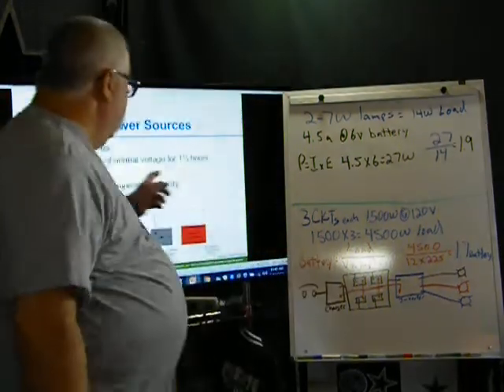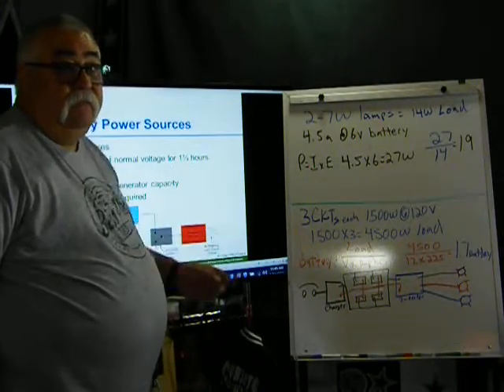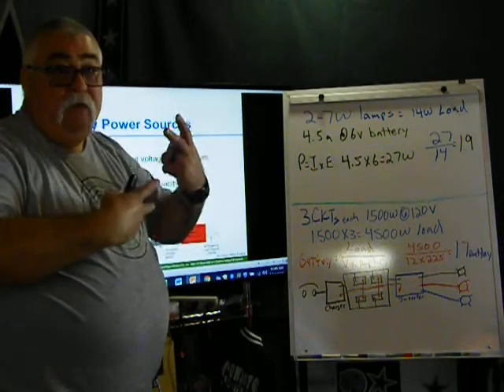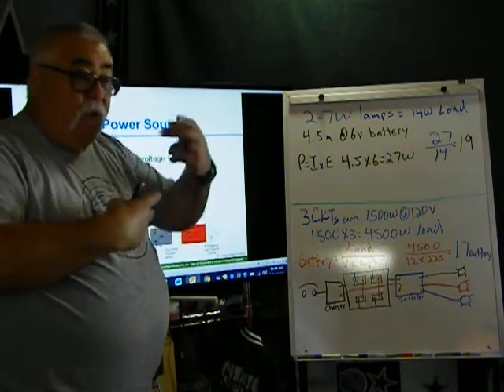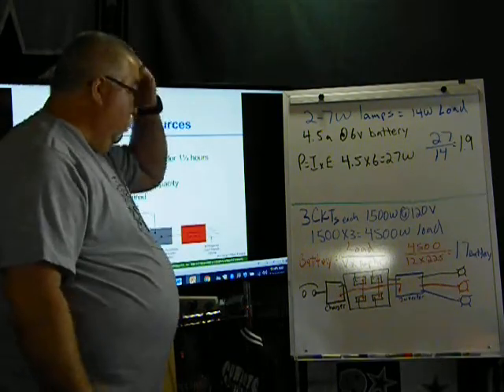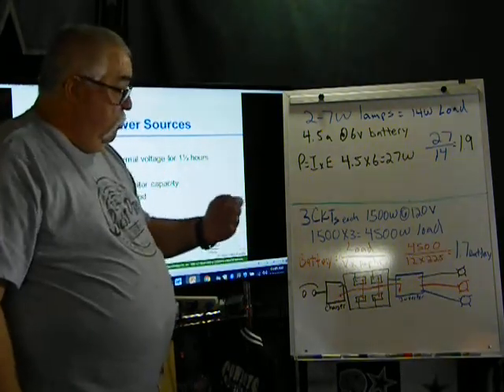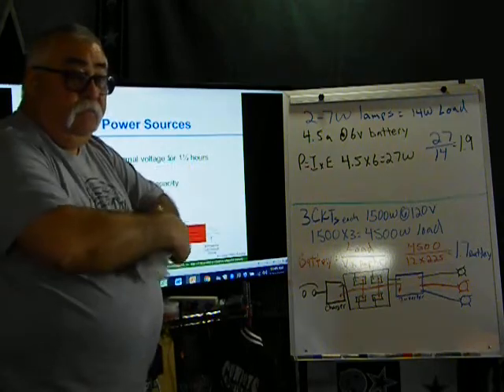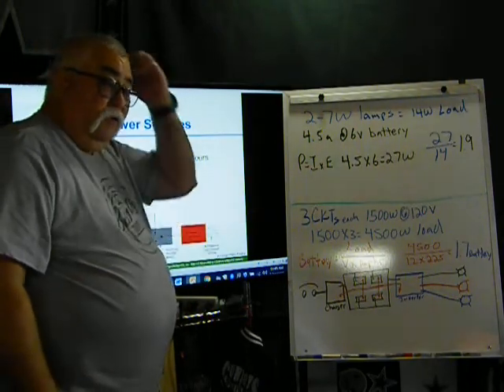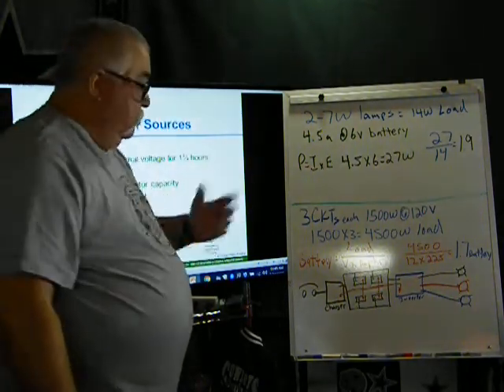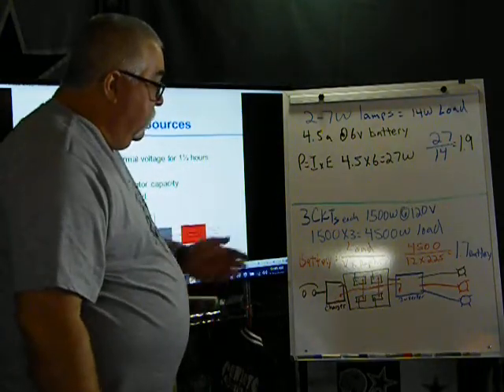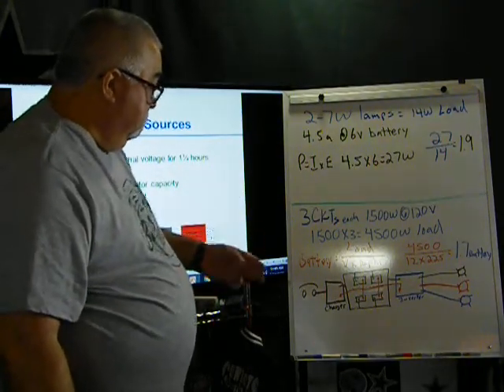But the code says I'm going to need an hour and a half. So what does that have to do? That means I have to double it. So now I'm going to have to double up my system. So now if I need 1.7 for 1 hour, in order to get it to 2 hours, there's going to be some losses in there. So it's always just wise to up it. So we go to the 2 batteries.